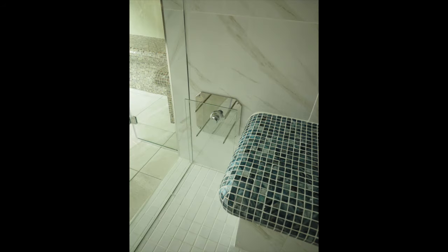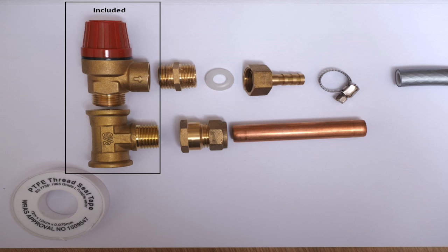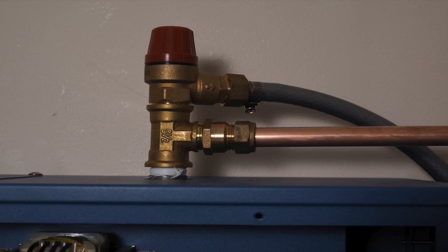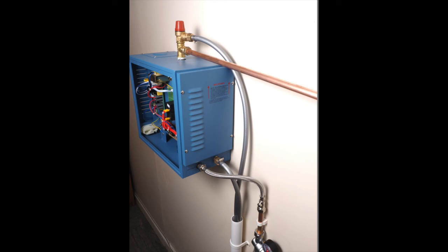The steam nozzle should be positioned 300 millimetres from the floor of the steam room, as far away from user's feet, a doorway or the temperature sensor. In this image, we show an example of how to pipe the top of the generator. The lower pipe which runs freely through the T-junction is the steam pipe which should be run in copper.